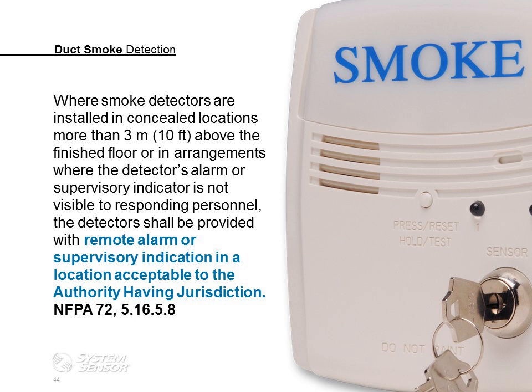Also, if you're in a commercial building that has a drop tile ceiling, you're not going to be able to see those indicators on the duct detector itself. So again, a remote alarm or supervisory indication is required anytime the duct detector is not readily visible and it's greater than 10 feet above the finished floor. What that really tells you is that you should be designing, selling, and installing duct detectors and remote indication devices, whatever version you sell, on almost a one-to-one basis.